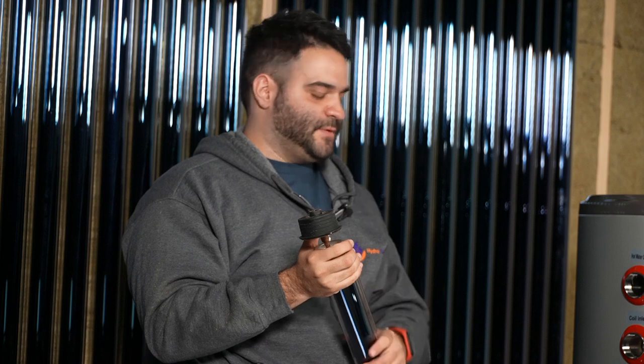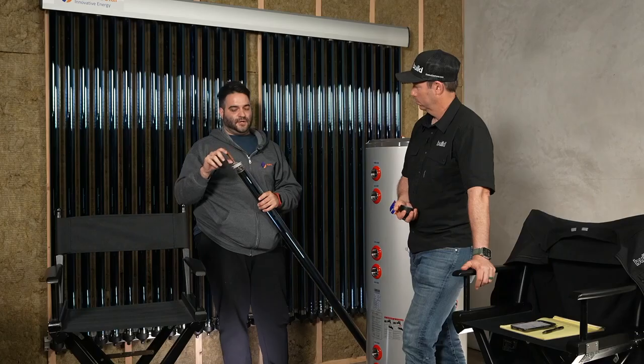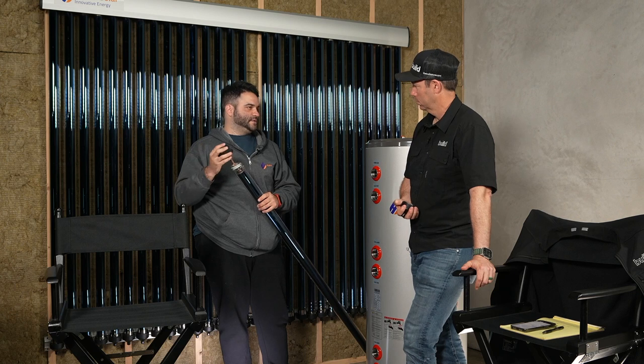So you can get just the glass part if the copper rod is still good. That's kind of cool. We recommend usually taking a look and replacing the whole assembly if it's closer to the 15-year mark, or if it got damaged, because the copper tubes themselves have corrosion that may happen over time.